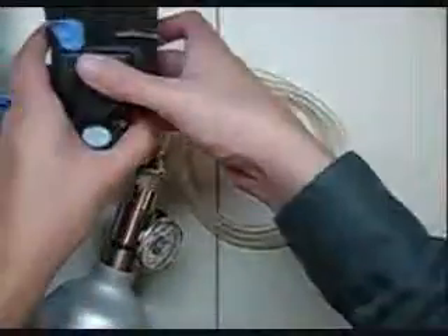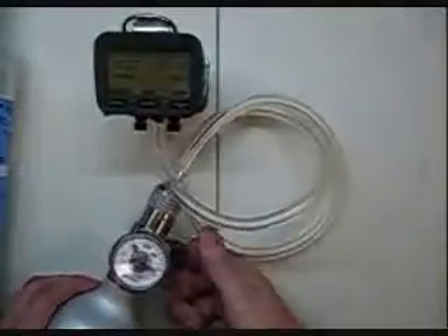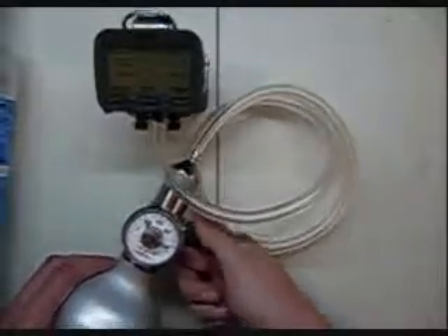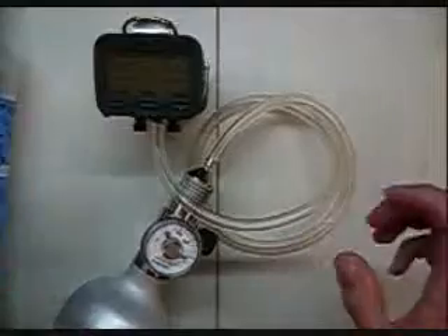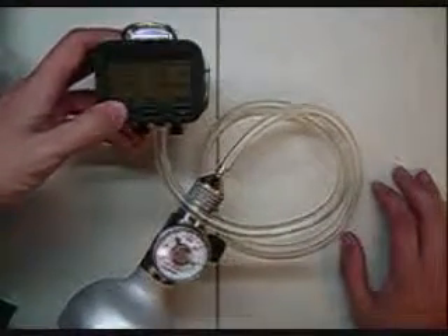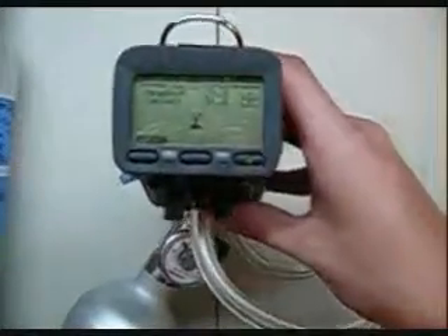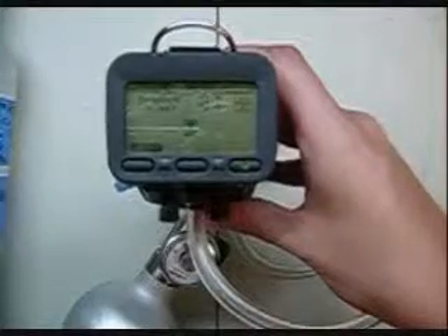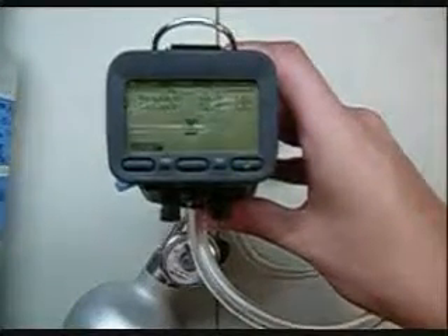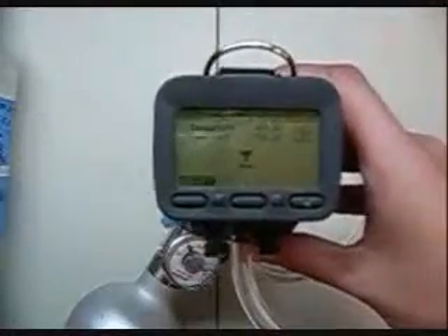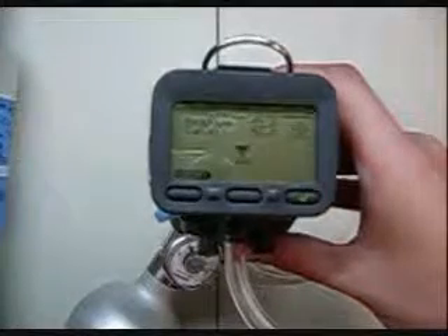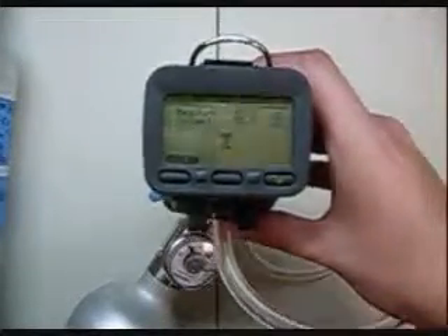What we'll do now is take our cal cap, screw it on here, and take our gas and attach it to the middle here, or the bottom one, sorry. And then we're going to turn our gas on. The first thing you're going to watch for is the readout starting to go up. As soon as you see something move, go ahead and hit start. Notice the little hourglass will begin, and you'll watch the readout going up. We're just going to put this one down until it stabilizes.